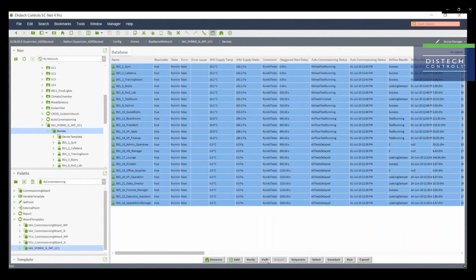Notice how each of the AHU supply temp and supply static values latch at the start of each new group. You will see the data continue to update throughout the test, and at the start of each new group, this will trigger a REST poll.